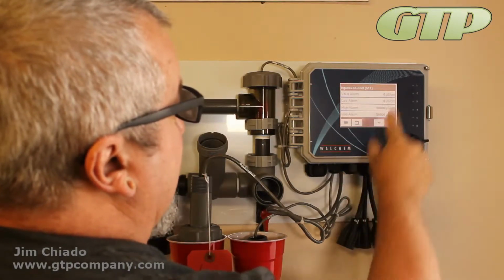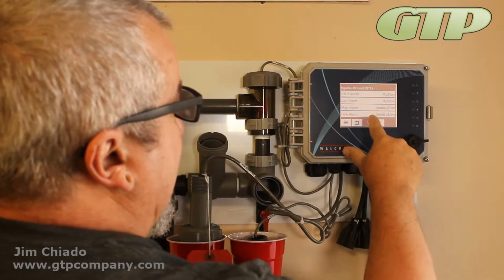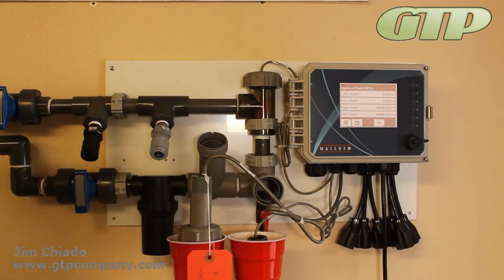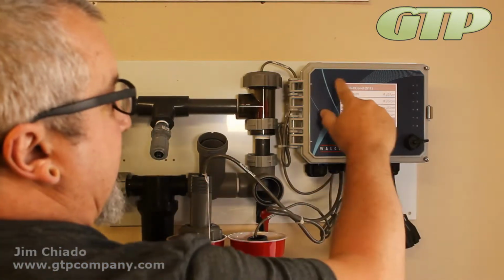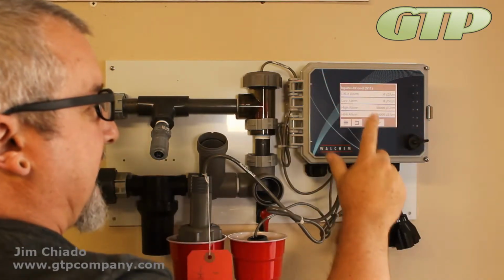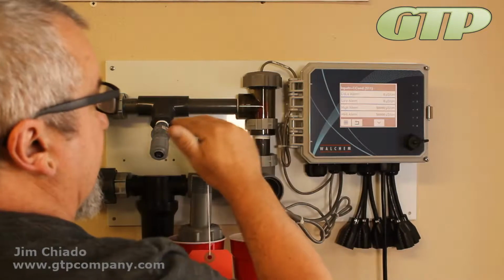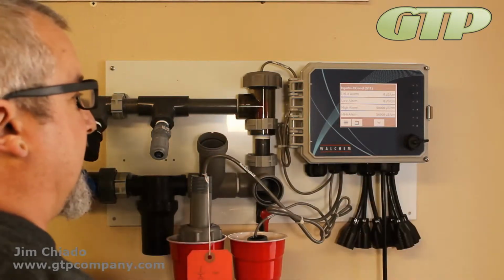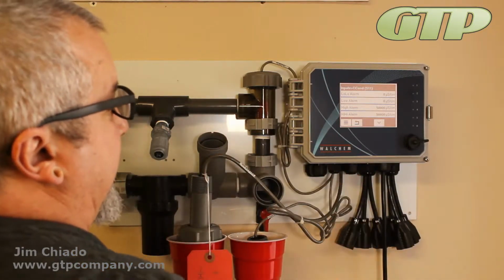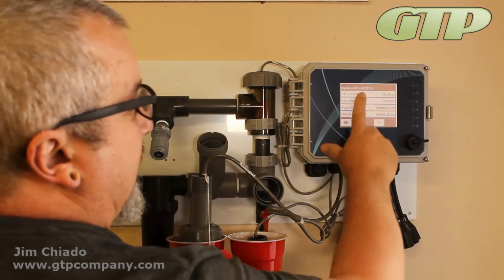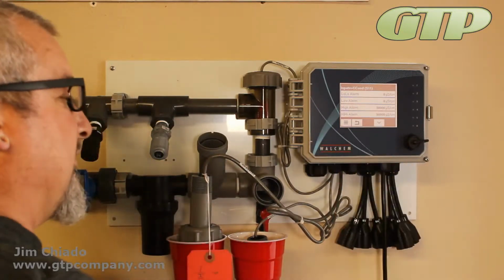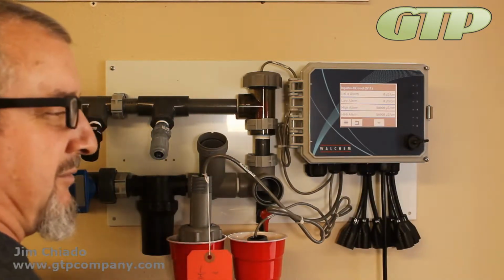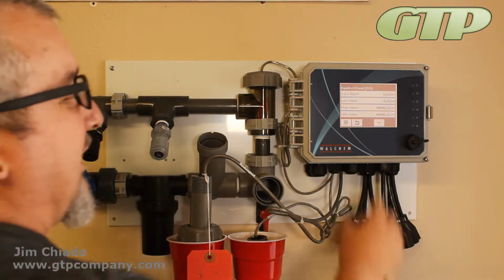So right now, connectivity, we're going to make sure that it's set up properly. Low alarms and high alarms. These really just give you the warning on the tops, but if you have this thing hooked to the internet and you know that, say, your city water is at 550, if you set something down at the 700 range, if this ever drops that low, you know that it's just making up, a valve is closed, stuff like that. So it really does make sense to set these things.